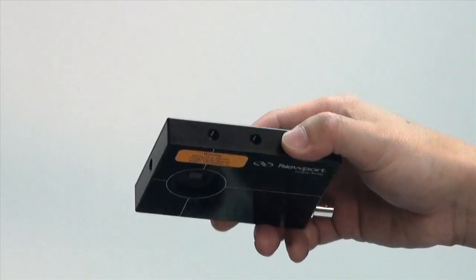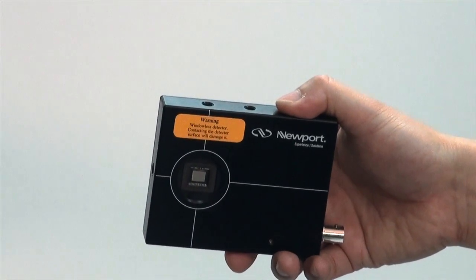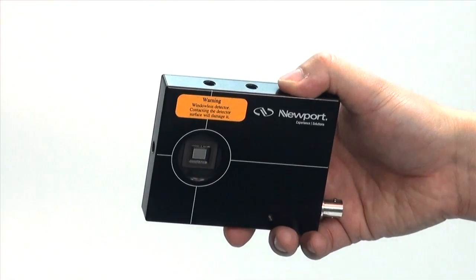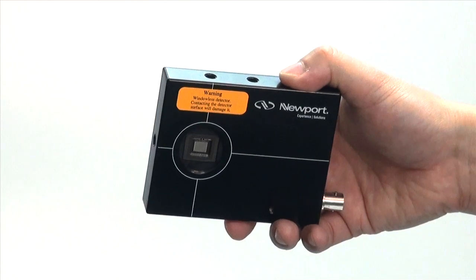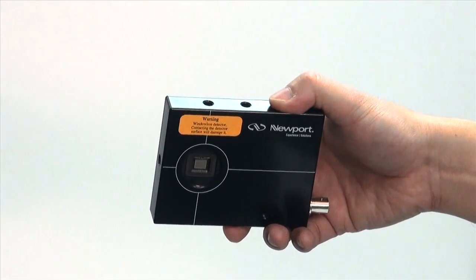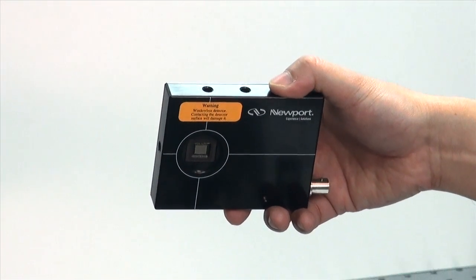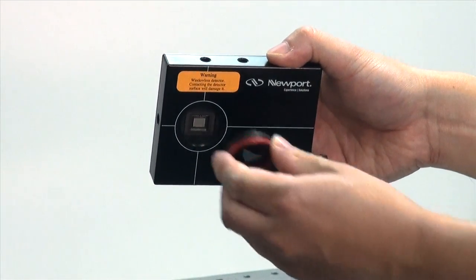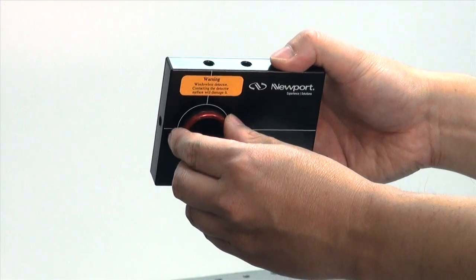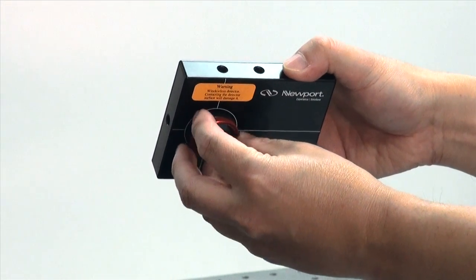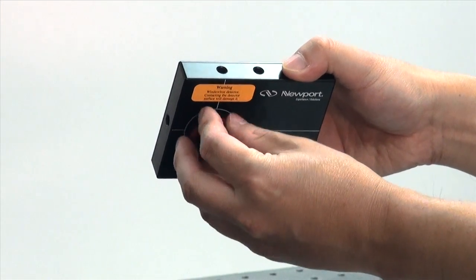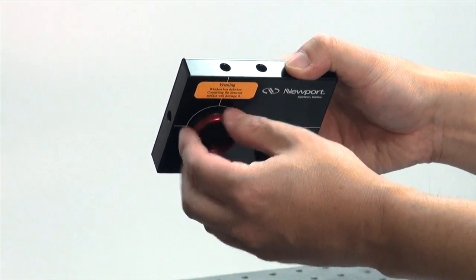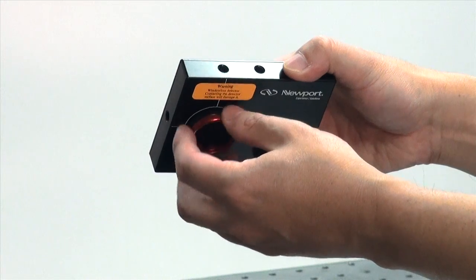Hold the camera upside down when removing or replacing any filter so that dust would not fall on the CCD. Use compressed air gently, not your breath, to dust off the detector if necessary. Never leave the detector exposed for a long period of time.